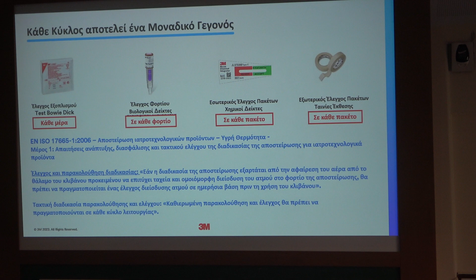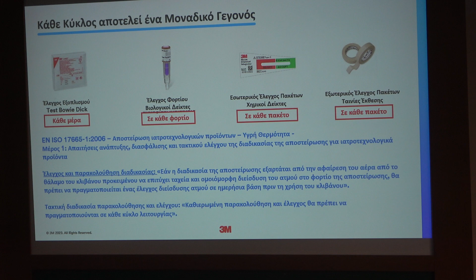Therefore, we have to remember that every cycle is unique, so every cycle should also be monitored. And I think we are all aware of the practices here about equipment control and everyday biological indicators to control the load, which means that if steam, for example, has the full killing ability for random microorganisms, every pack will need an internal indicator, because we always need to see if this killing steam is really taking place at pack level. And sometimes, of course, we are using pouches and reels, but when we are using wrapping materials, we need to have external indicators to show whether the pack has been exposed to the steam conditions or not.